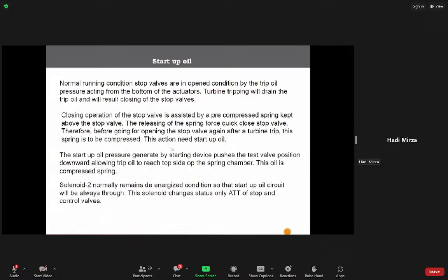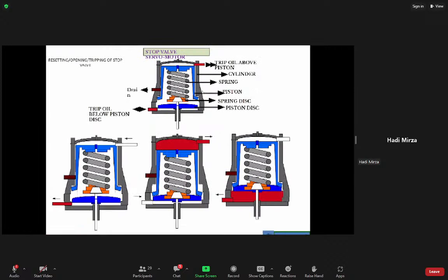The release of the spring force quick-closes the stop valve. Therefore, before opening the stop valve again after a turbine trip, this spring has to be compressed. The action needs the startup oil. Basically, it is a reset of the startup. Startup oil is used for resetting the stop valves and hydraulic trip devices. I have already explained this regarding RTS.